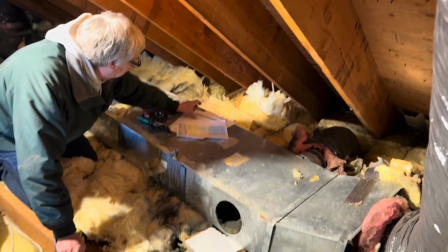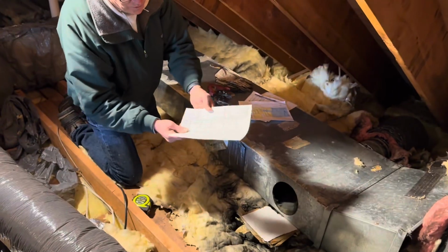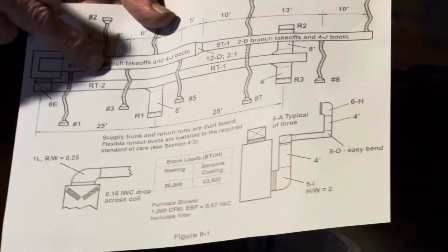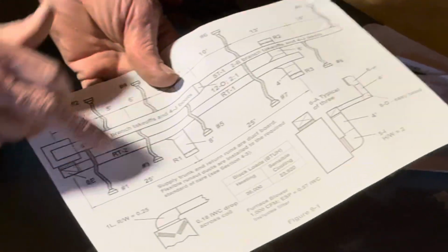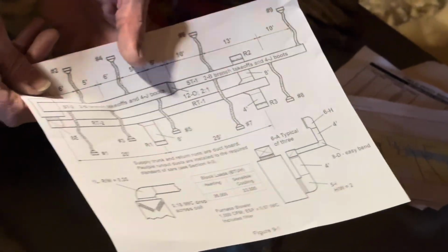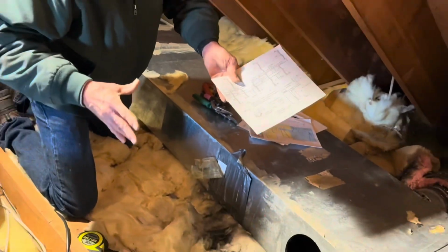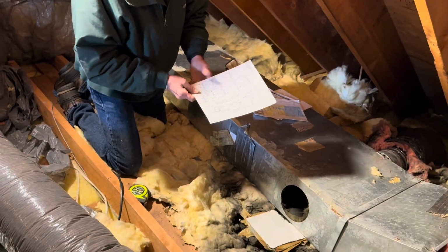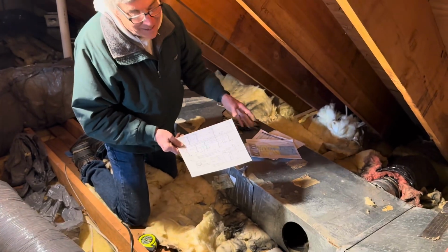In the design of this system, we will see that we start with a larger duct and then we go to a smaller duct. And the reason that we do that is because when we have each one of these takeoffs of the branch circuits, we're going to lose some of this air. So if we start with a larger size like we do over here, and then we go to a smaller size later, we'll maintain a constant pressure, the same pressure. This is done on a computer, and it's designed so that we can properly design the duct system.